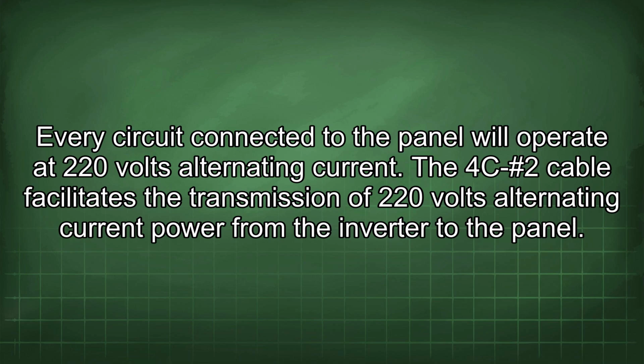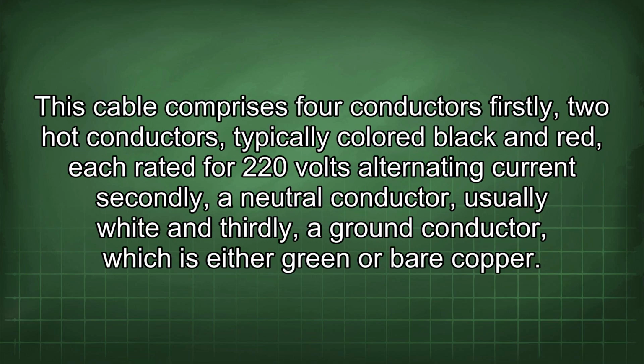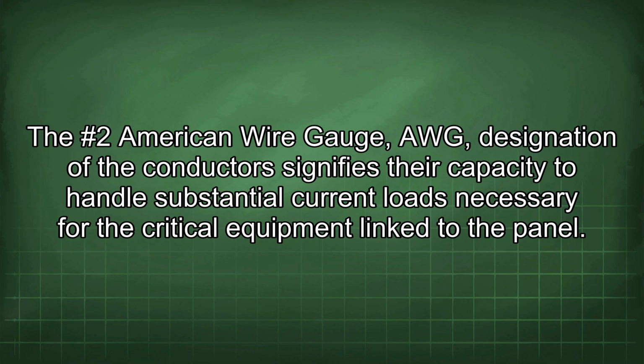The 4C-2 cable facilitates the transmission of 220 volts alternating current power from the inverter to the panel. This cable comprises 4 conductors. Firstly, 2 hot conductors, typically colored black and red, each rated for 220 volts alternating current. Secondly, a neutral conductor, usually white, and thirdly, a ground conductor, which is either green or bare copper. The #2 American wire gauge, AWG, designation of the conductors signifies their capacity to handle substantial current loads necessary for the critical equipment linked to the panel.